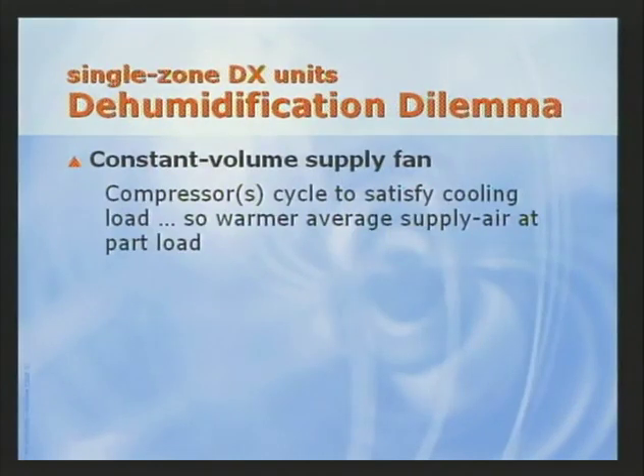Now, similar to the earlier example, the combination of a constant volume supply fan and a compressor that cycles on and off results in a warmer average coil surface and a warmer supply air temperature at part load conditions. Again, this results in less dehumidification and elevated space humidity levels. Applications with high ventilation requirements, such as school classrooms, can pose a significant dehumidification challenge for some constant volume DX units. More outdoor air, especially in hot, humid climates, requires more cooling capacity, or tons.